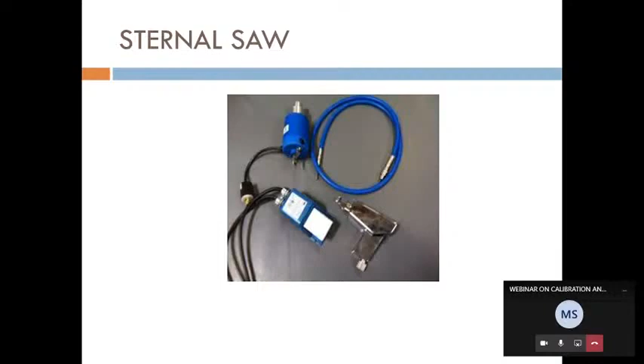First thing, if the saw is not working, you change the cable. After changing the cable, if it is working, then the problem was with the cable. After changing the cable, if it is not working, then you need to change the saw head. After changing the saw head, if it is working, then the problem is with the saw head. Okay, this is the sternal saw.